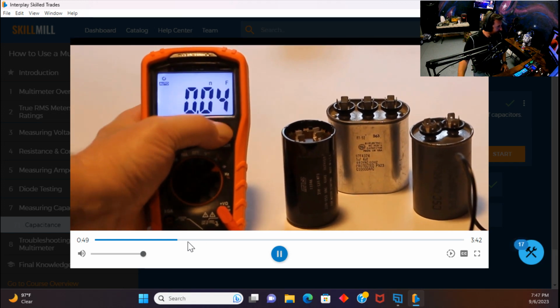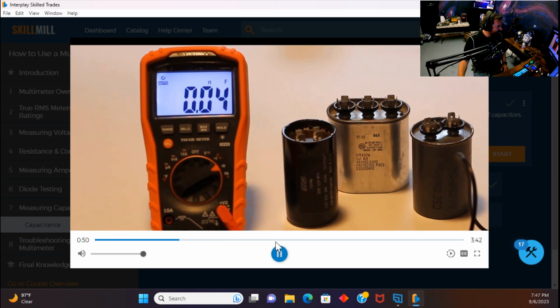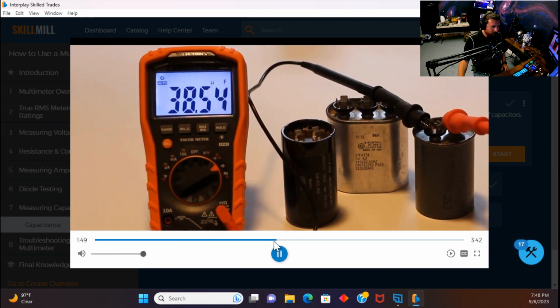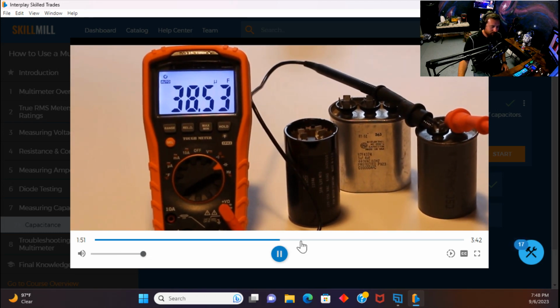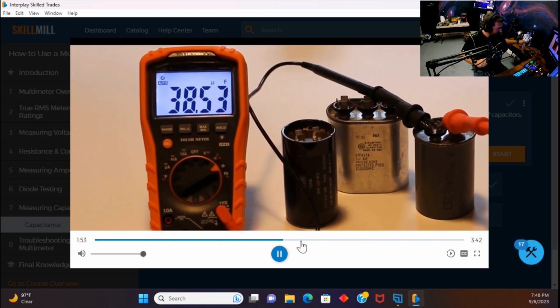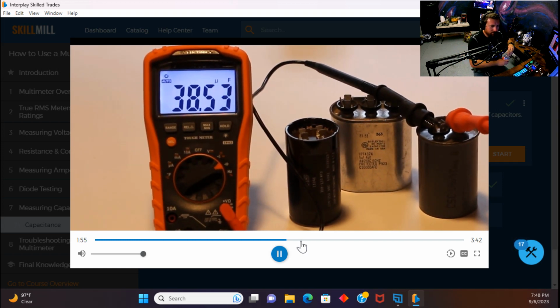Light on, so that we can see the display a little bit. On the meter, we can see that we have 38.5 microfarads. Now this capacitor is rated for 40 microfarads, so that's okay. With run capacitors, you want to be within plus or minus 10% of the rating on the capacitor. So again, it's that simple.